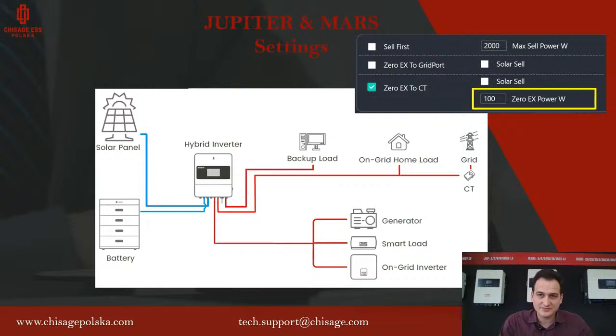And then, similar to the zero export to grid port, we have the solar sell option. So if I have more than enough, I can sell. If I secure the backup load, the on-grid home load, and charge the battery with maximum power, or the battery is fully charged, I can sell to the grid. We also have the value, like now in the yellow frame it is 100, zero export power in watts. That's the power the inverter will always buy from the grid, because the on-grid home load is always changing. So the inverter will try to produce as much energy as the on-grid home loads need.